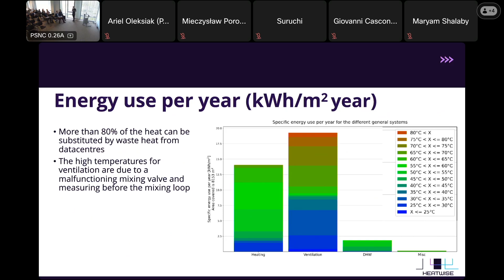We see that more than 80% of the heat can be substituted by waste heat from data centers. And of course, when you start digging into buildings, there is always faults that you discover, and we also found it in this case. The very high temperatures for ventilation are due to a malfunctioning mixing valve - this was what we measured coming into the ventilation system, but it was not necessary, it was just a faulty valve. So this part here is not necessary. But you will encounter that when you go out in buildings - there's always something that doesn't work according to plan.